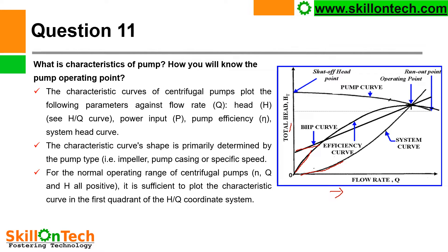So let us know where the operating point of the pump is. You can see in this picture: this is the HQ curve going like this, and this is the system head curve. Where these two curves intersect — that point is called the operating point of the pump.